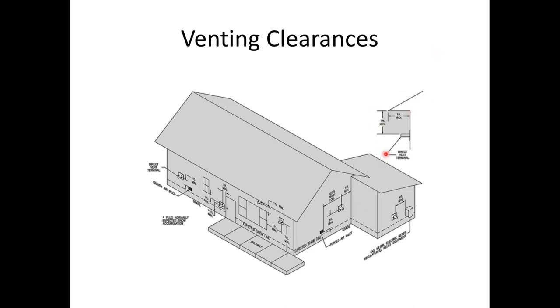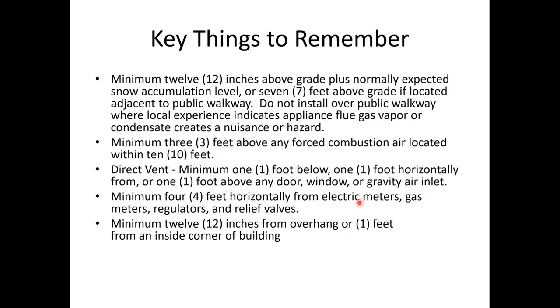Our overhang clearances, if you're coming out on the eaves or over any overhangs: 12 inches out, 12 inches below, 24 inches out, 24 inches below, and so on. A few things to remember with it. Again, 7 feet above grade if it's adjacent to a public walkway. You don't want to install over an area where your vapor will create a condensate hazard where it will make it slippery. And we'll stay out of an inside corner of a building. The inside corners usually result in recirculation, and recirculation does some pretty nasty things to these products.